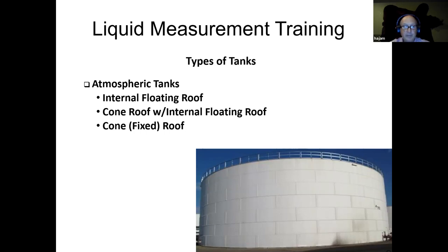Also, in these floating roof tanks, there's always a way to drain the water. I don't mention that here, but we want to make sure that the floating roof doesn't have any water on it, because that will affect the level of the crude oil in the tank. Any extra weight on that roof will throw your level off. So just some things to be aware of.